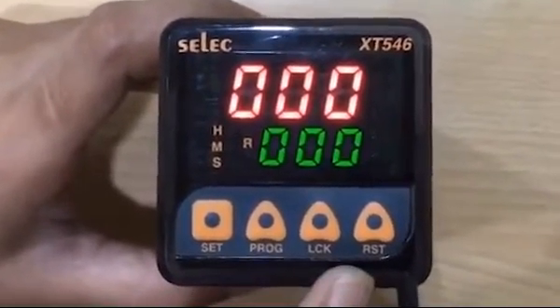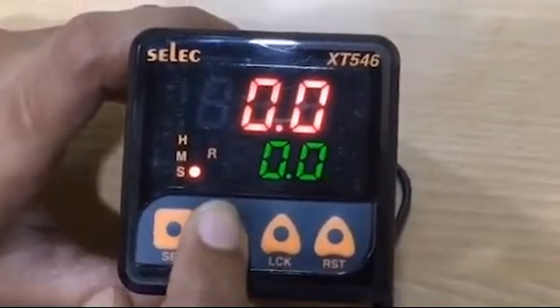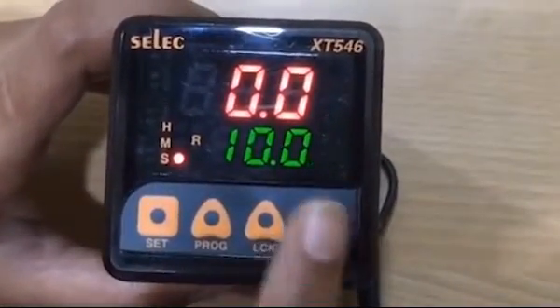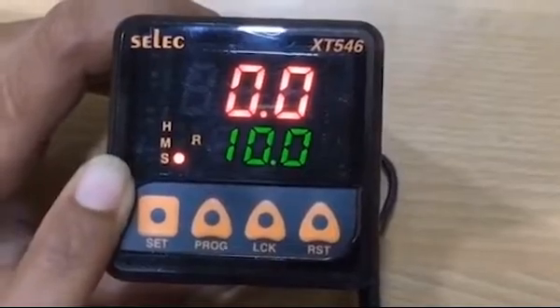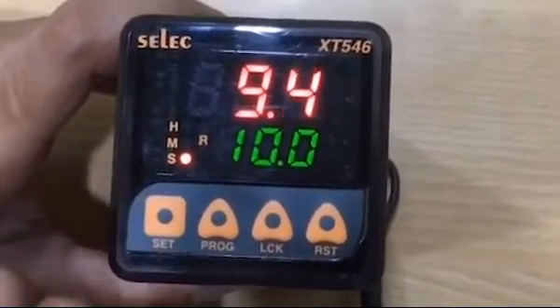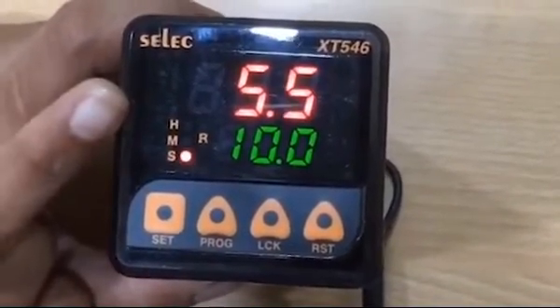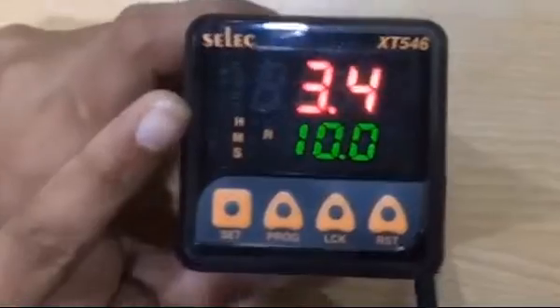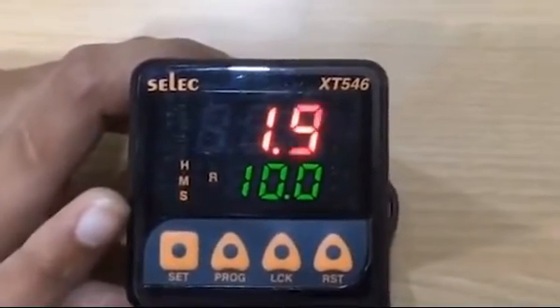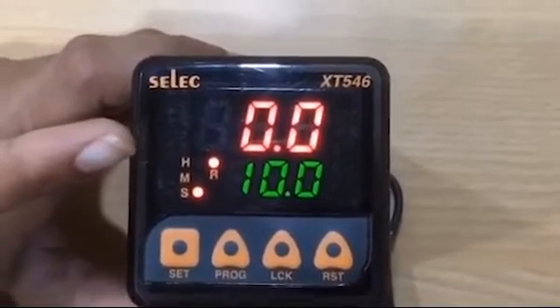To set time, press PROG key to change the set value. The corresponding digit will increment from 0 to 9 and then will roll over back to 0. For example, let's set the time as 10 seconds. Press set key to store set value. After pressing the set key, time starts and as it is in on delay mode, after the set time elapsed, the relay will get on. R indication shows relay condition, whether on or off.